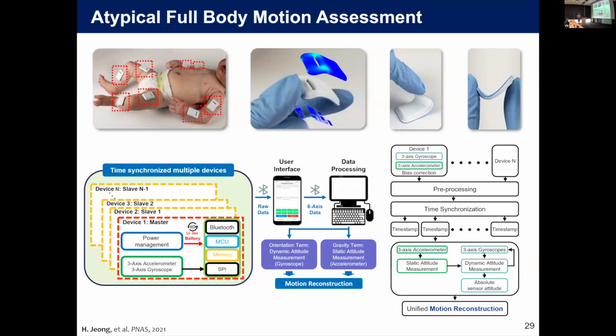And a slightly similar platform, but I use multiple devices. So this one has Bluetooth communication, memory, and power, and this one is for the newborn baby. We specifically added the safety part as well. The safety part means monitoring the temperature, current, or voltage inside the device. So if the temperature severely increases, then the safety circuit just cuts the power to the whole device. Because the newborn baby cannot say, oh, my device is hot, so we focus on the safety part as well.